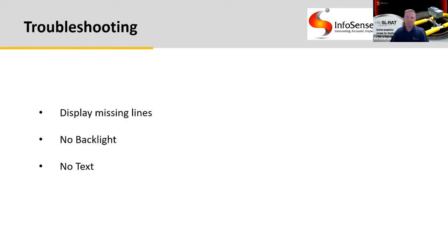If you're having a display issue, the screen might need to be replaced. You can change the contrast and brightness to try to make it more viewable, but that's about it. There is a middle range default that prevents you from turning the brightness all the way up or all the way down and then turning the unit off. It will reset when you power the device on, so you can again see the screen.